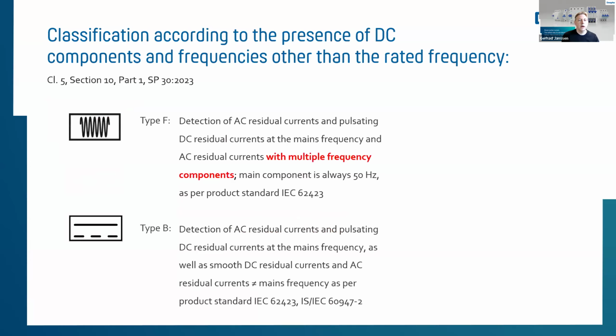The next type, to have even additional protection additionally to AC and DC currents, is a type F, which is also covering different frequency components, unequal 50 cycles. So if you have meanwhile applications or loads where one phase or single phase frequency converters are involved, you will see it afterwards, then a type F should be the minimum requirement. And all of our new modern households have a lot of those applications inside of it. So type F should be as well interesting.